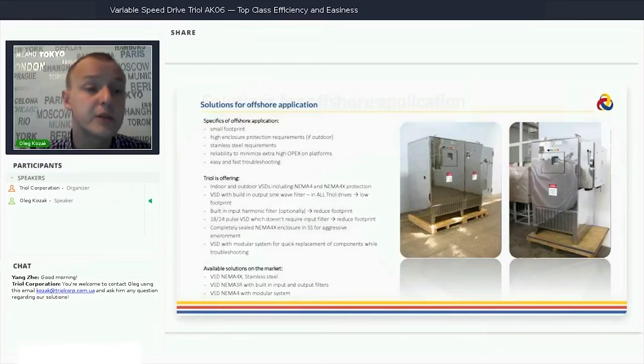Another solution used in Southeast Asia is the 18 or 24 pulse, which doesn't require any input filter at all. You just need a phase shift transformer, the VSD, a sine wave filter which is also built into our drives, and a step up transformer as well. That's all. And we have a completely sealed NEMA 4X enclosure with stainless steel for aggressive environments.